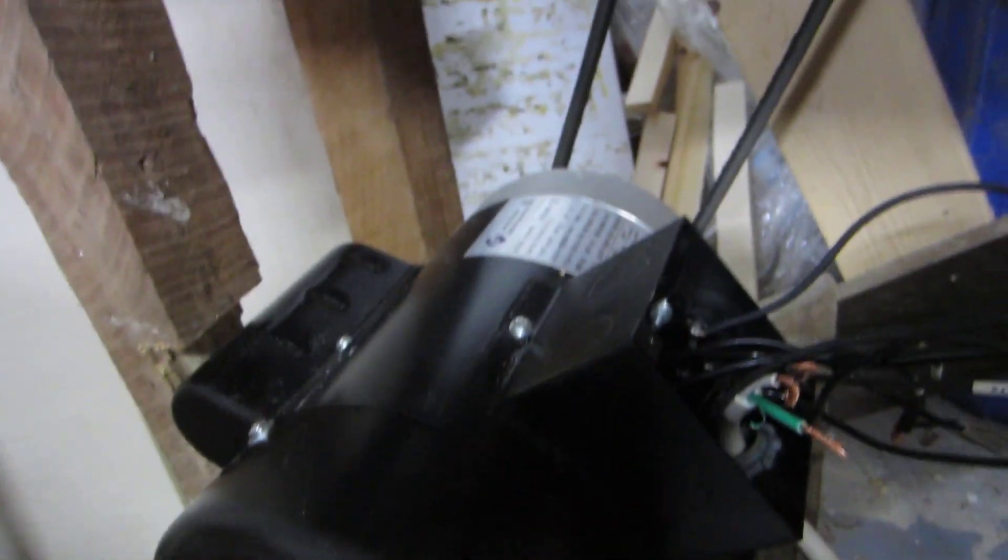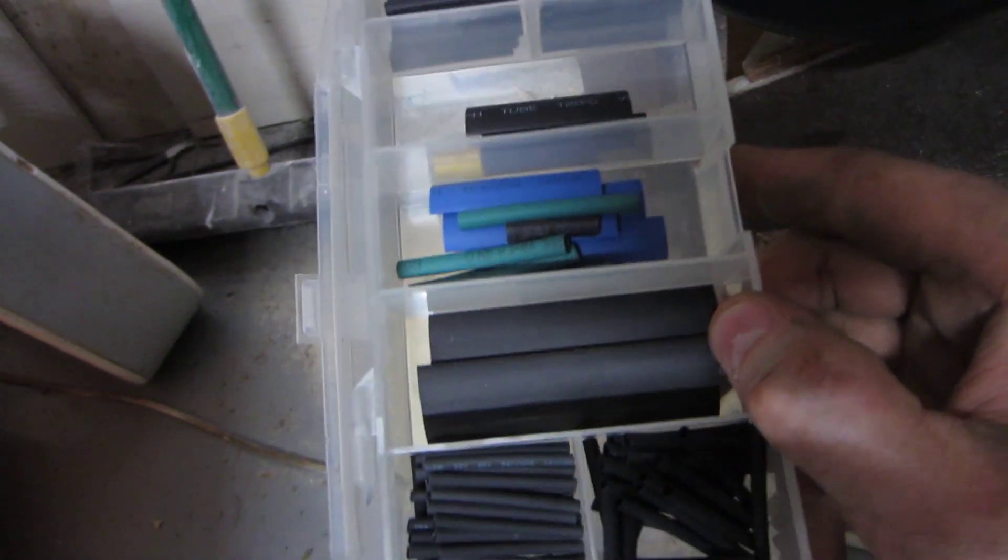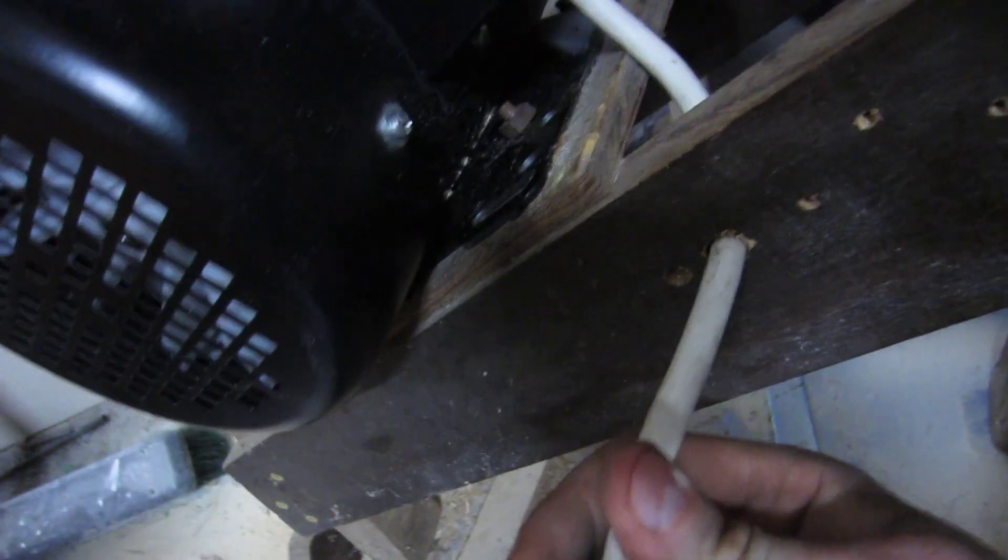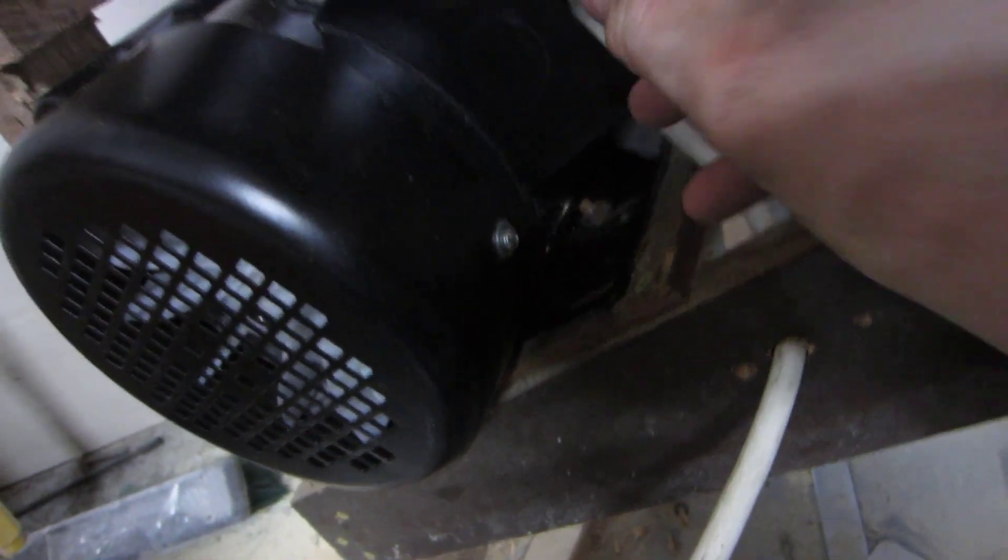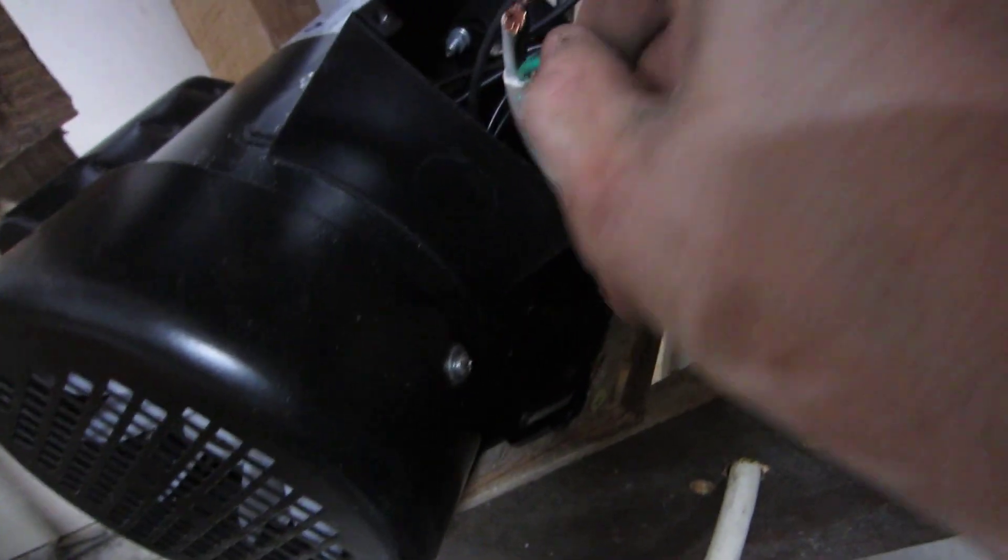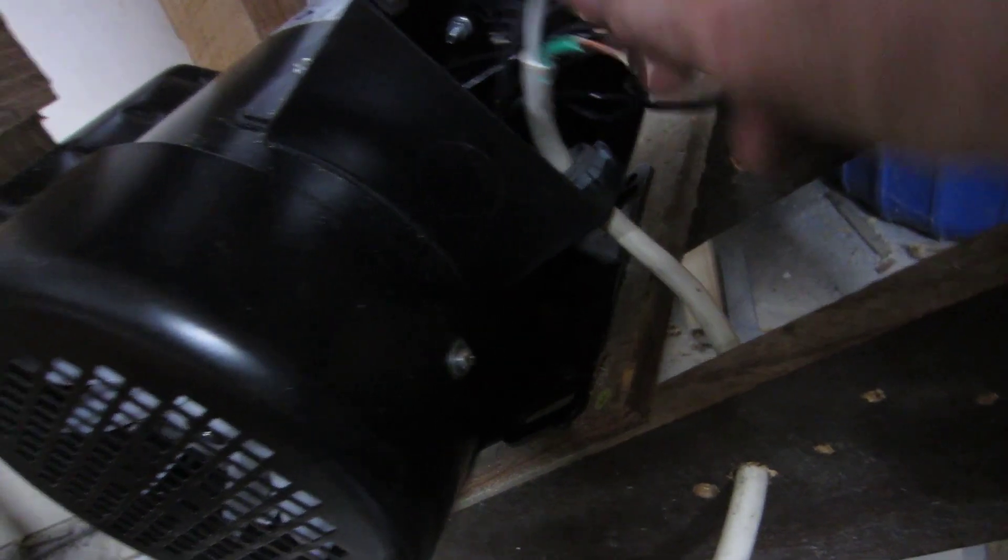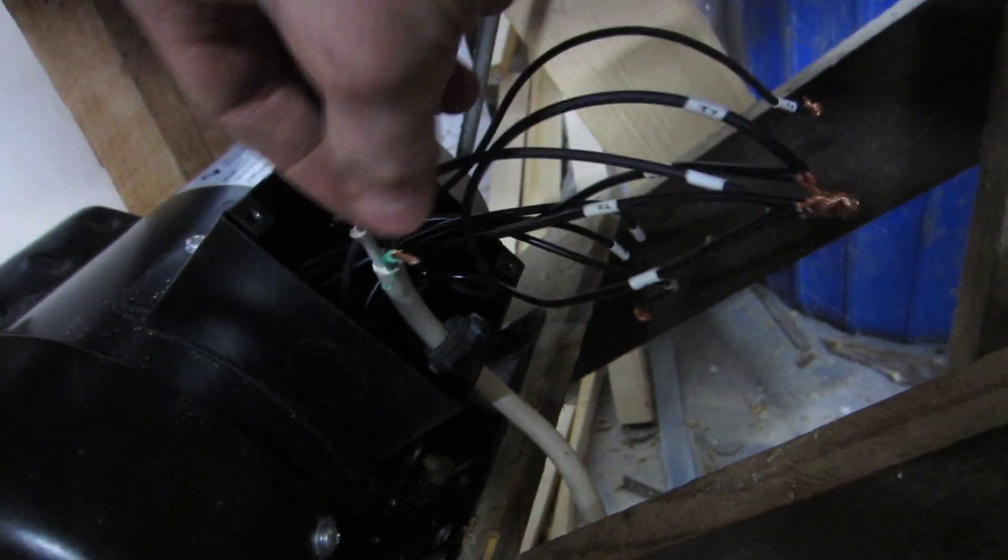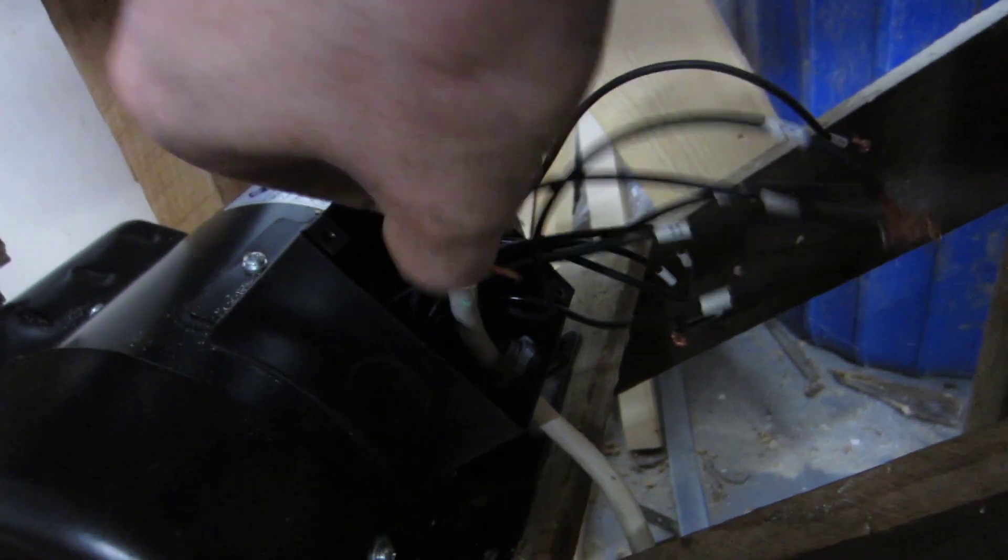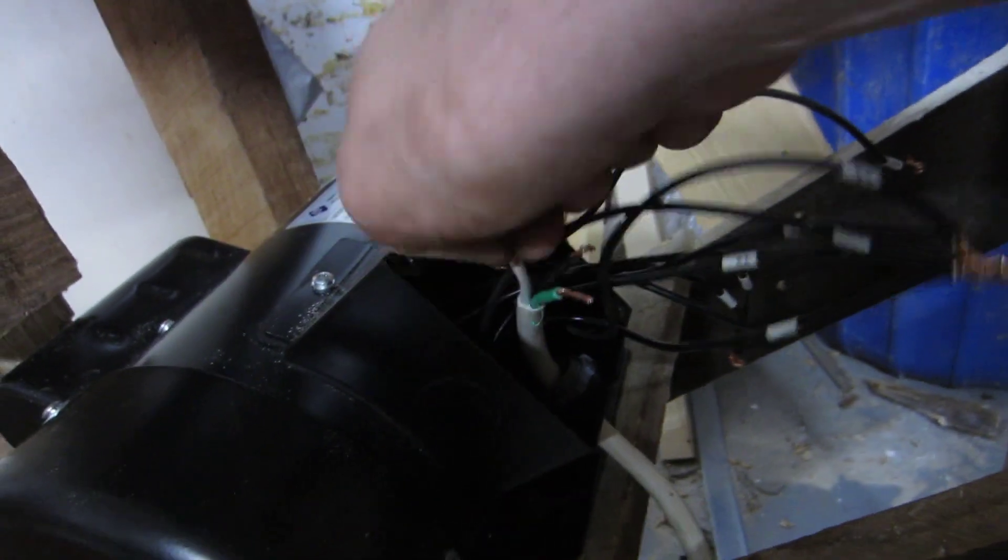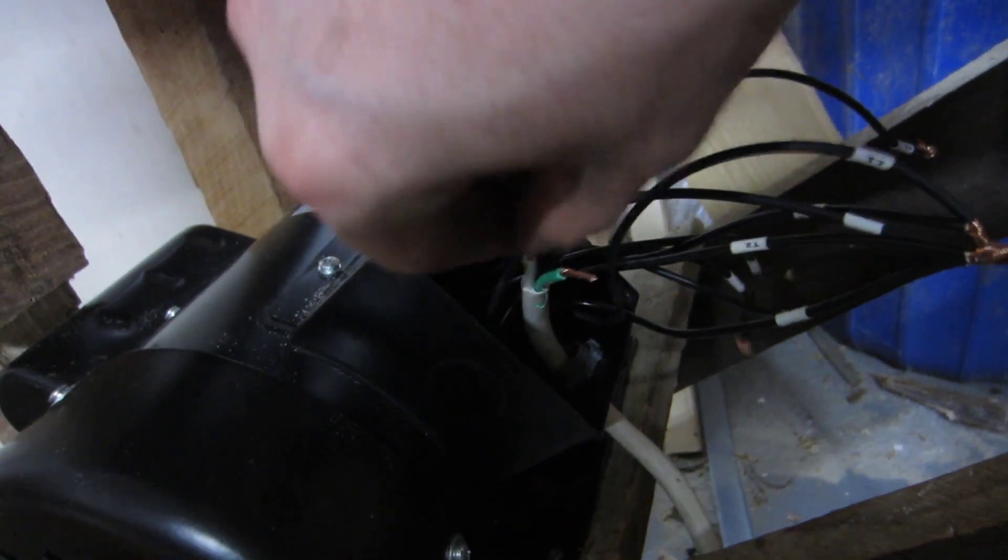What I'll do is I'll go ahead and ground the case with my green line here. I'm gonna use a bunch of heat shrink on here. A few things you would need if you were doing this: the first thing is I upgraded my line over here to 14 gauge which can support 15 amps. The other line I think was probably 16 gauge, which would have potentially worked fine because this is only 11 amps, but since I could bump it up I decided to go ahead and do that.